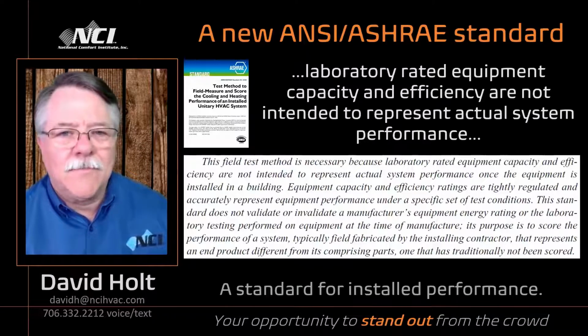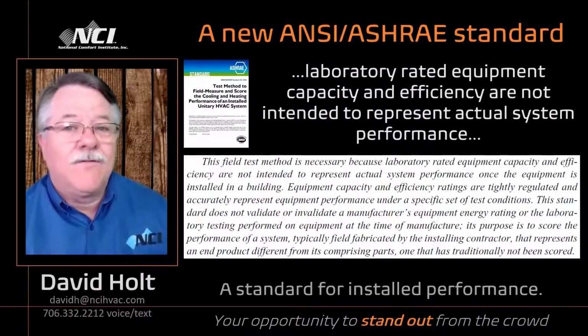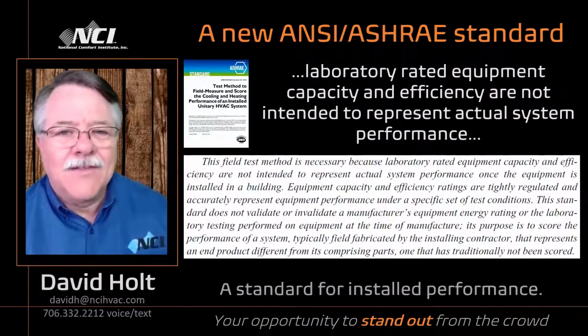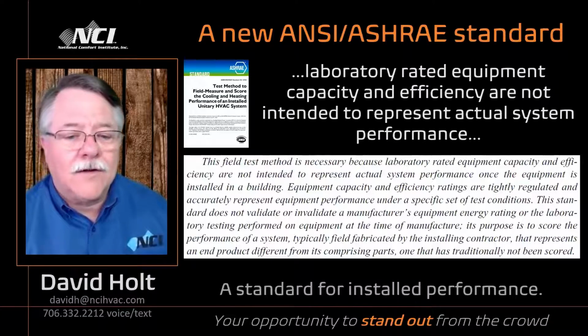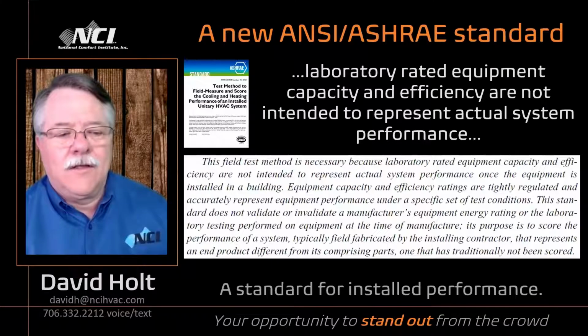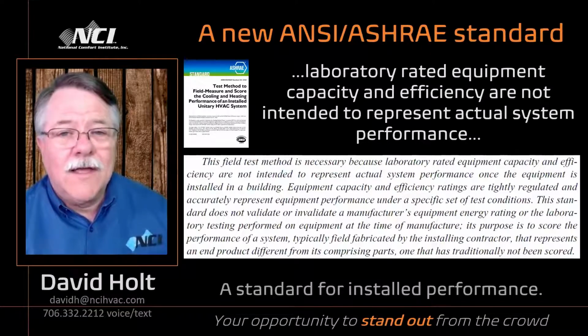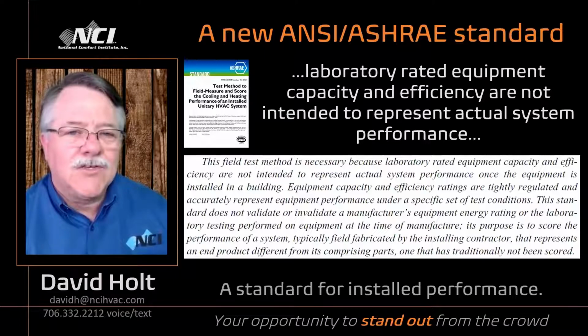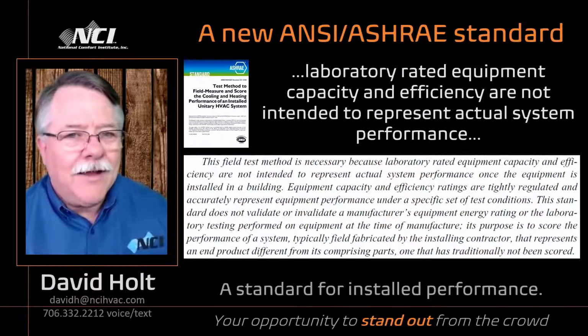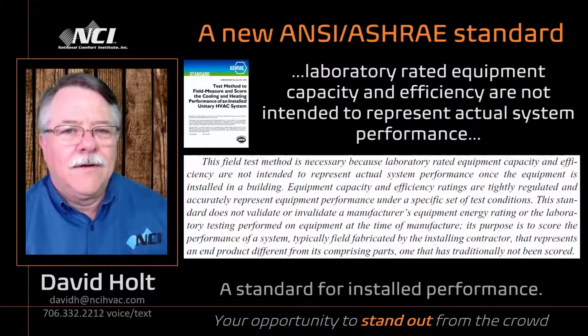All these components are just that. They're components. And what this standard does is it helps us measure the performance of the system from grills and registers all the way back through to the equipment, fabricated, designed, installed by us, by the installing contractor. That represents an end product different from its comprising parts. Okay, think about that. Our end product, the complete HVAC system, is different than the individual parts. So the testing and rating standards that we've been operating under in this industry for years don't actually apply to as installed. Think about that.